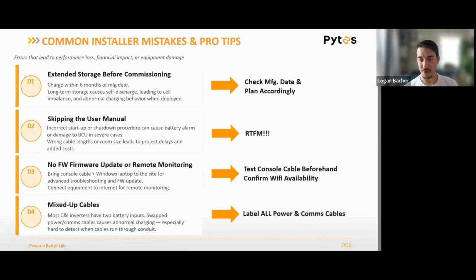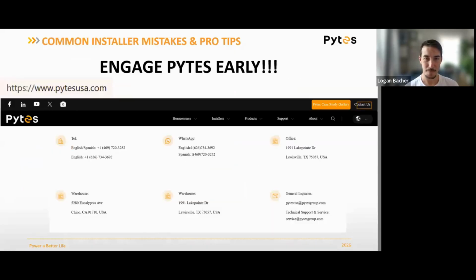This next one's a little more minor, but simple things like labeling the cables matter. A lot of these high voltage inverters have two battery inputs, so you can imagine you've got two cabinets connected to one inverter. I've got some examples on that coming up, but just label everything - take that extra few minutes to label the power cables, label the comms cables. I can't tell you how many hours I've spent troubleshooting a problem only to find out somebody just flip-flopped the BMS cables at the inverter. Sounds really trivial, but it helps save a lot of headache at the end of the day.